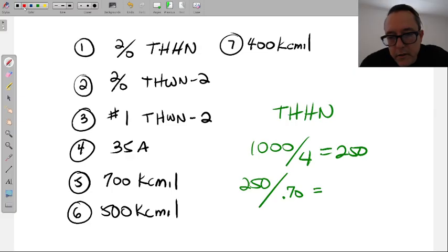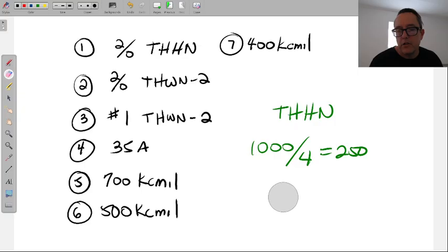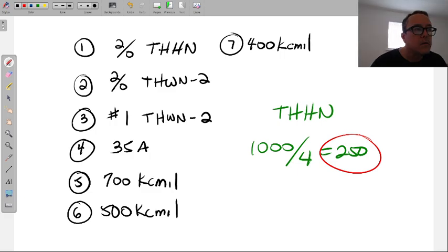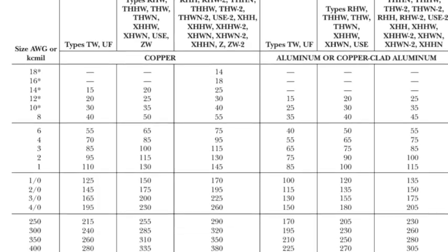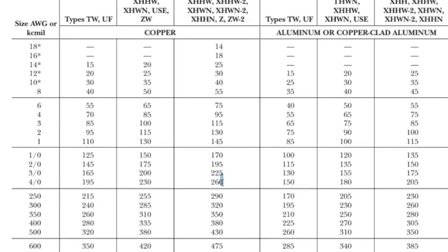Absolutely. So first things first, again, let's deal with one half of the question first. We're only trying to figure out 4 parallel conductors for 1,000 amps. So 250 amps would work. 4 wires that can hold 250 amps. We're in the THHN column. So if we head over to the THHN column with that 250 amp goal, then the 260 would be fine. The 4-aught would be good.